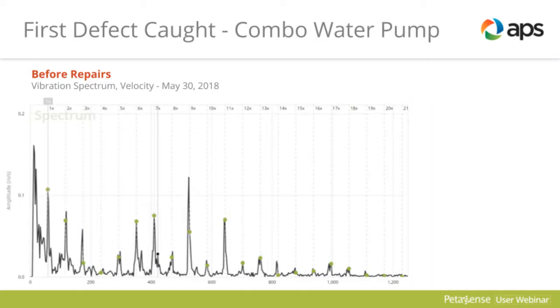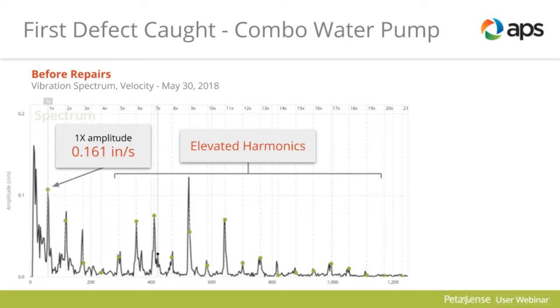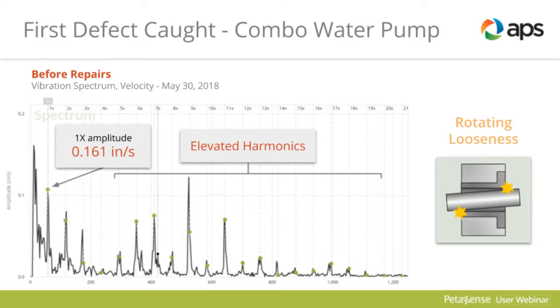This is actually the Petasense reading. If you can see, the pump has later stages of journal bearing wear. There's evidence by the presence of a whole series of speed harmonics, the one-time speed harmonics. Rotating looseness is caused by the excessive clearance between the rotating and stationary parts of the machine.